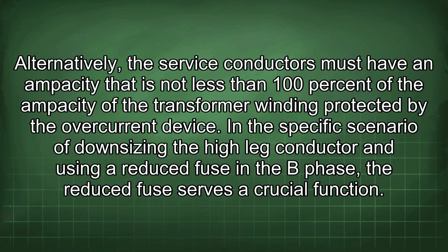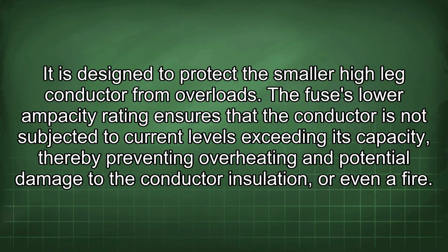In this specific scenario of downsizing the high leg conductor and using a reduced fuse in the B phase, the reduced fuse serves a crucial function. It is designed to protect the smaller high leg conductor from overloads. The fuse's lower ampacity rating ensures that the conductor is not subjected to current levels exceeding its capacity, thereby preventing overheating and potential damage to the conductor insulation, or even a fire.